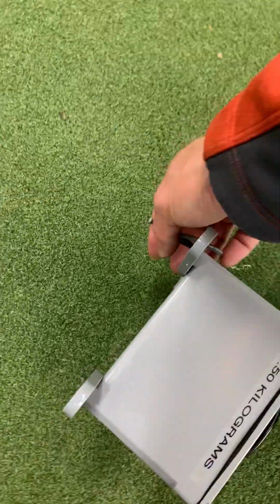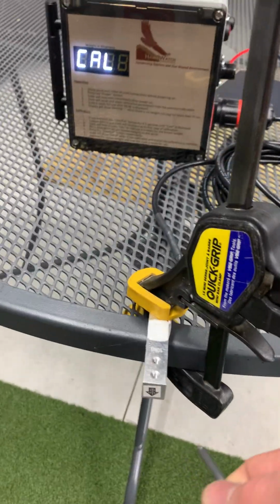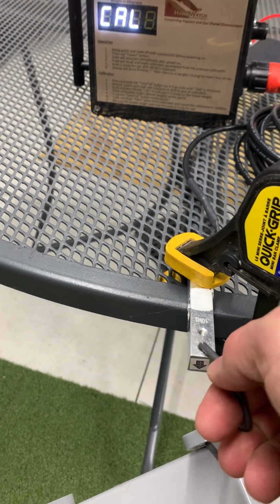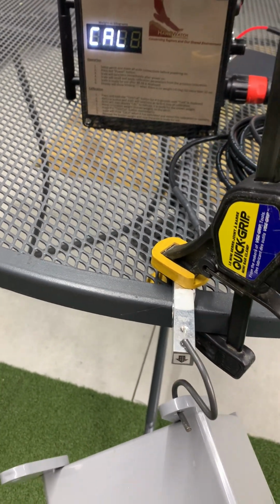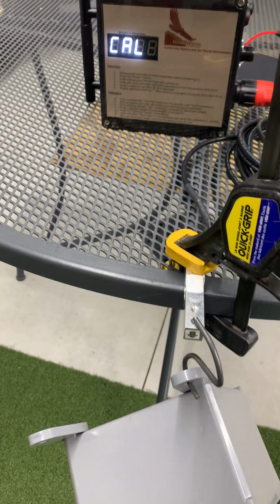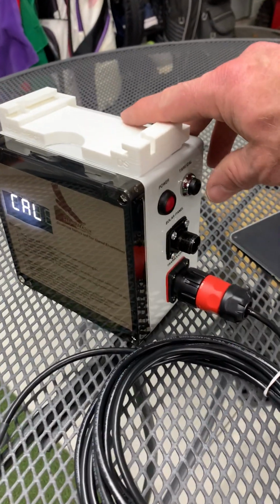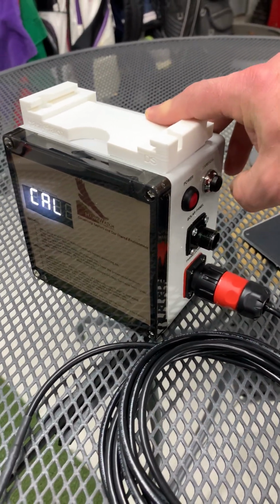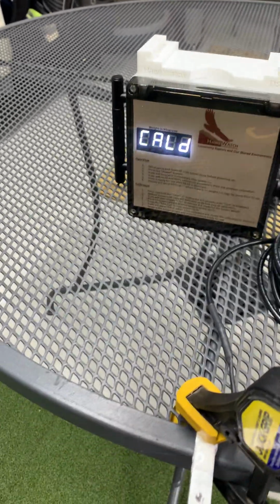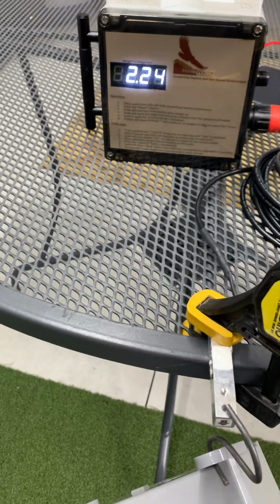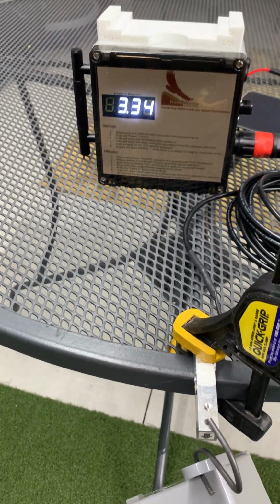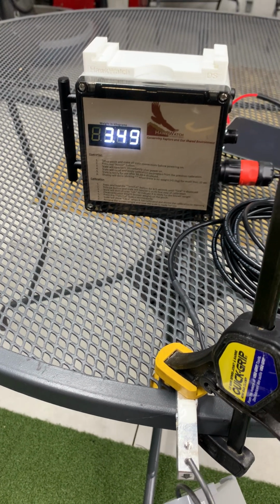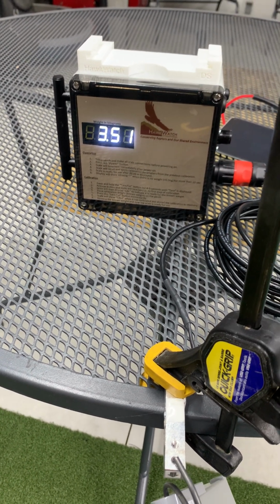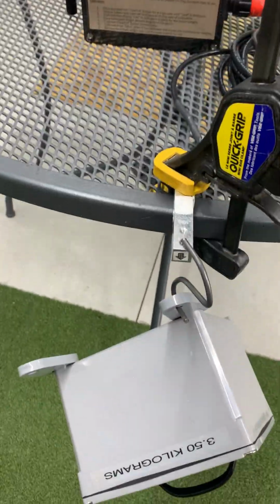You hang your 3.5 kilogram weight on there. This thing's really flexing. Then you hit the button again and it'll say CAL'd. Now it's calibrated. And you can leave it on there to check your calibration. It's rocking a little, so it might be a touch off, yeah.